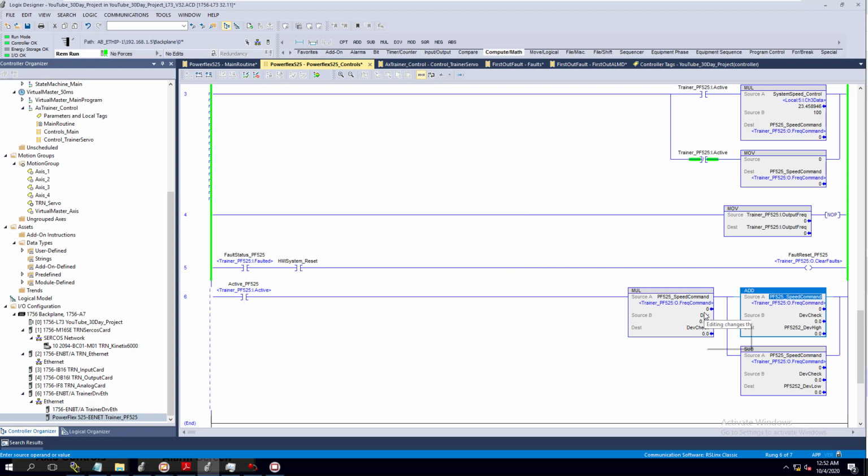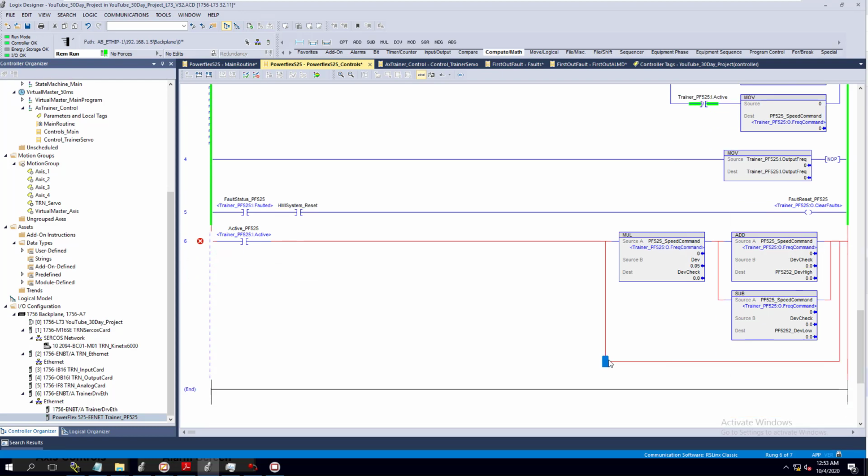And as we're doing that, we're going to add some more logic. Let's just add this real quick. The point behind what we're doing is trying to see if there's a deviation. Think about this: this is a loaded system, and it's not a system that you would generally have a feedback on, like an encoder or something like that. But it is a system that you would still want to monitor to see if there's a stall or something. So this is where you would use this.